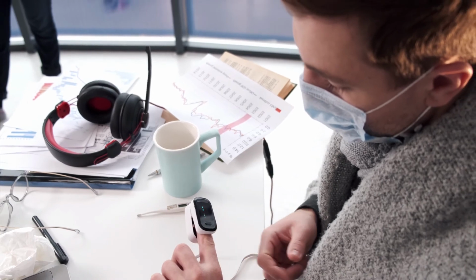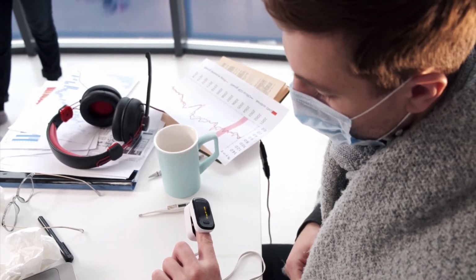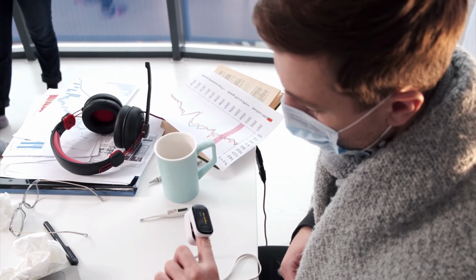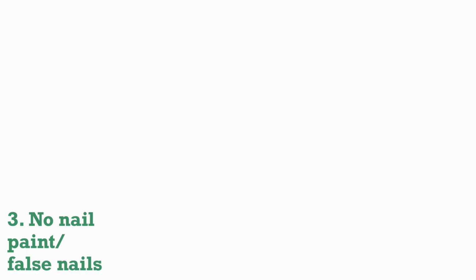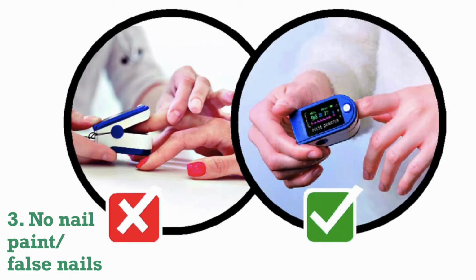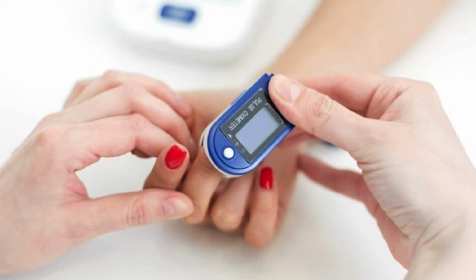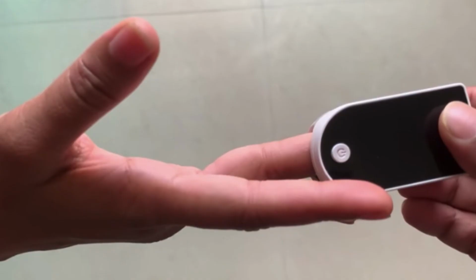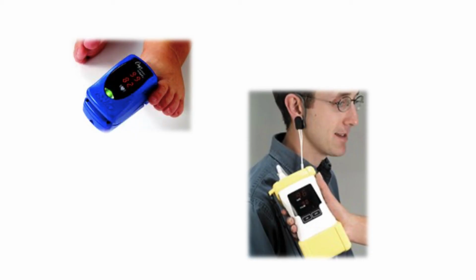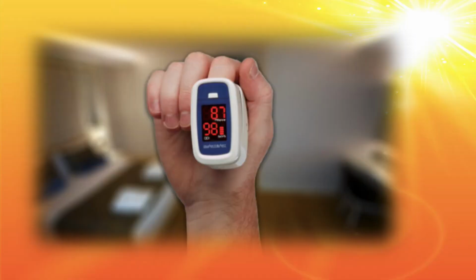Otherwise the pulse oximeter might not work, or other light comes in, and that will affect the final readings. The next one is no nail paint or false nails. Nail paint absorbs light emitted by the oximeter, so it should be removed before using it. Or the probe may be turned sideways in case of emergency, or select a toe or earlobe for SpO2.